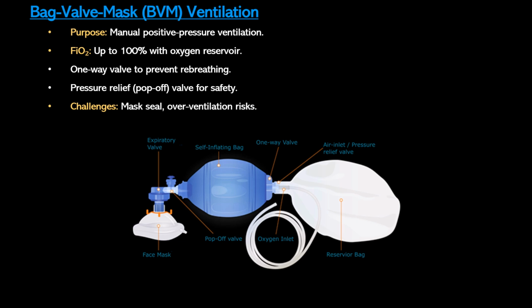The bag valve mask, or BVM, is a go-to tool for manually providing positive pressure ventilation to patients who can't breathe effectively on their own. When connected to supplemental oxygen, it can deliver nearly 100% FiO2, making it extremely effective in emergencies where high oxygen levels are needed. The design includes key components like a one-way valve, which ensures the patient gets fresh air with each breath and prevents exhaled air from contaminating the bag. Most BVMs also have a pressure relief valve, sometimes called a pop-off valve, which limits the airway pressure to avoid lung injury. This feature is especially helpful in pediatric patients, but can be overridden when higher pressures are needed for ventilation.